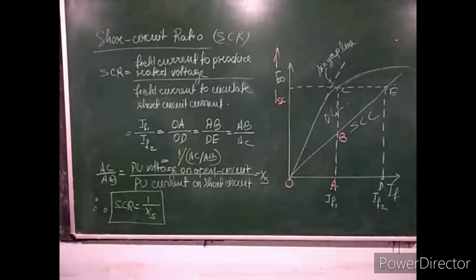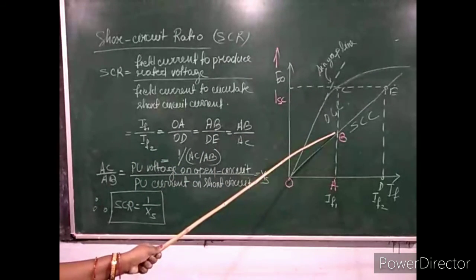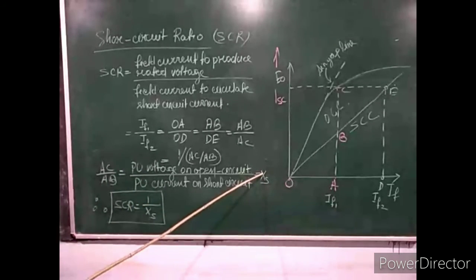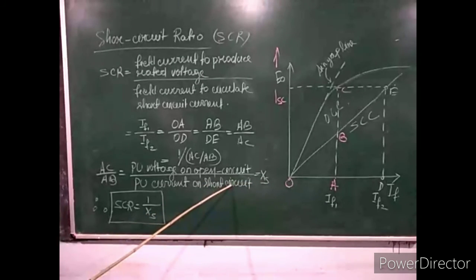And a small value of SCR, SCR meaning the short circuit ratio, indicates a smaller value of current under short circuit condition due to the large value of synchronous reactance. From this relation it is very clear now. If the synchronous reactance is large, it means the short circuit current is less, the per unit short circuit current is less.